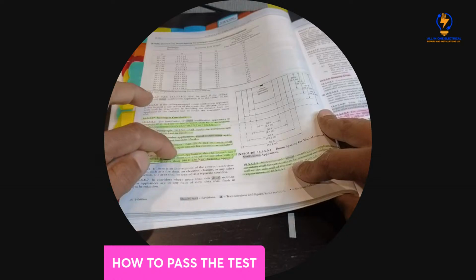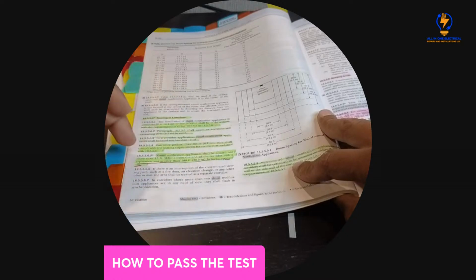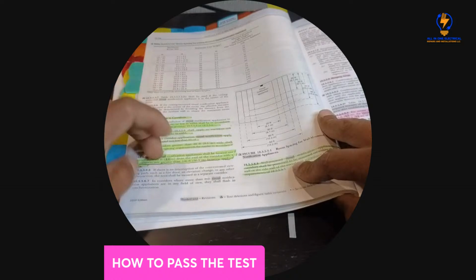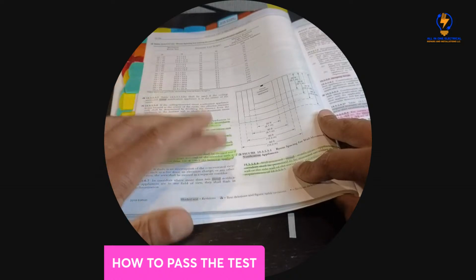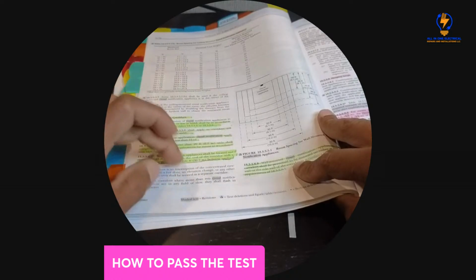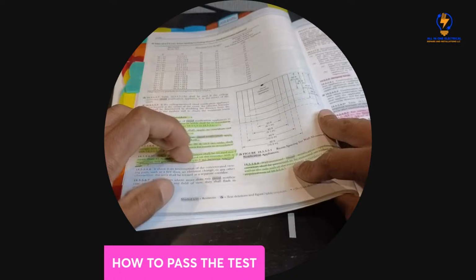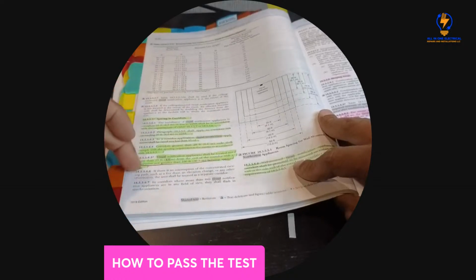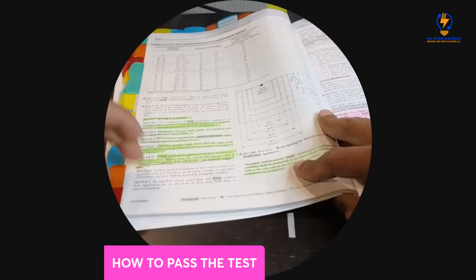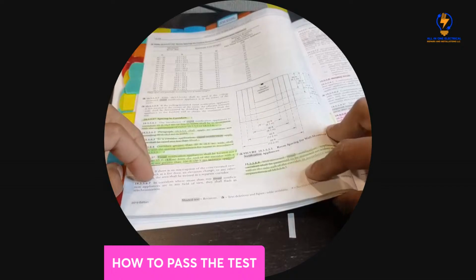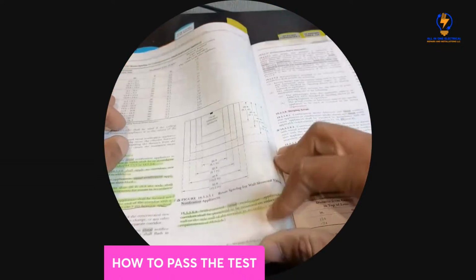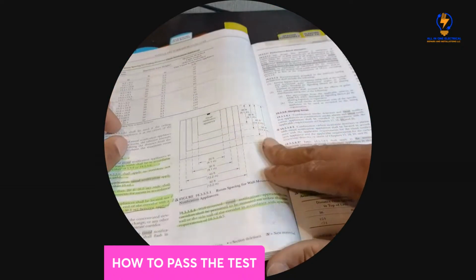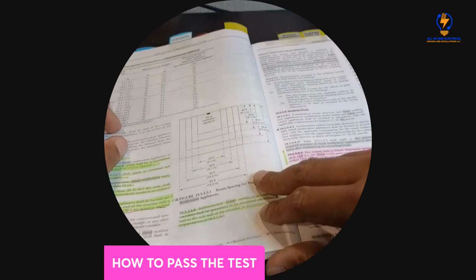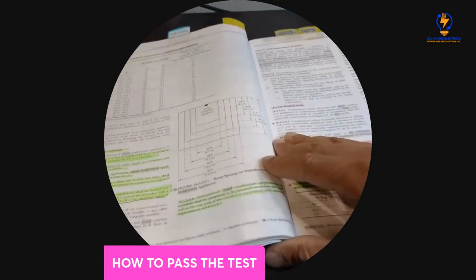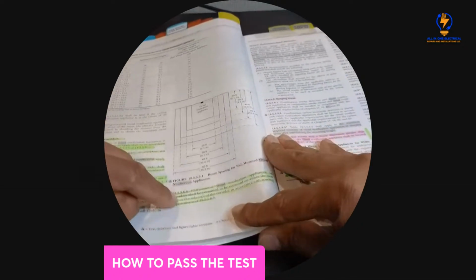At the end it says visual notification appliances shall be located not more than 15 feet from the end of the corridor, with a separation not greater than 100 feet between appliances. Very important. This is a test question. For the ones that don't know, they will ask you stuff for NFPA 72. A lot.